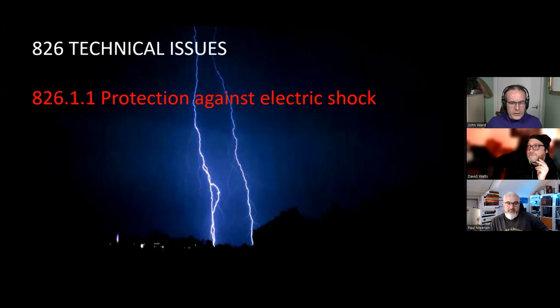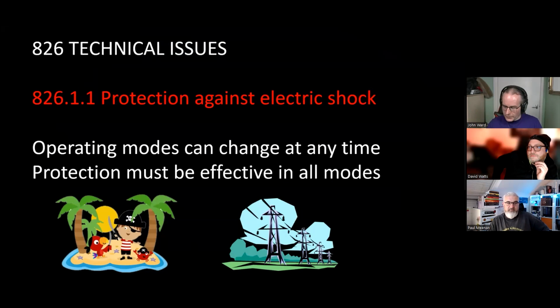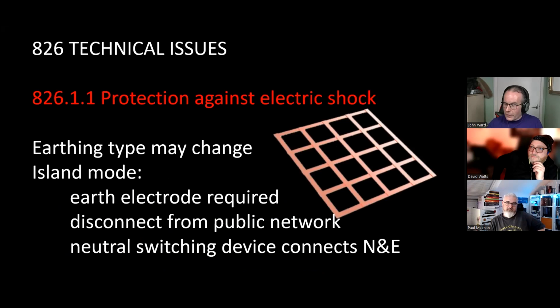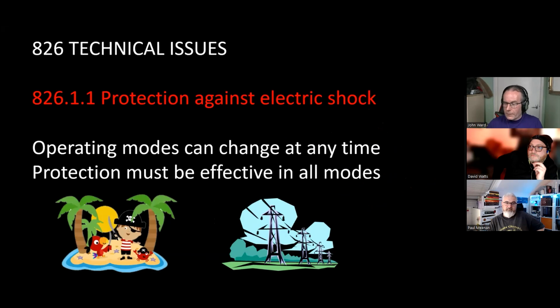Now 826, this covers some technical issues with these things. So first one of which is protection against electric shock. A lot of this is similar to the other things there. One of the main differences is that the operating mode, whether you're in island mode on your own or connected to the grid, this can change at any time, and whatever protection you've got in there against electric shock must be effective in all of the modes. So, to continue on that one, yes.